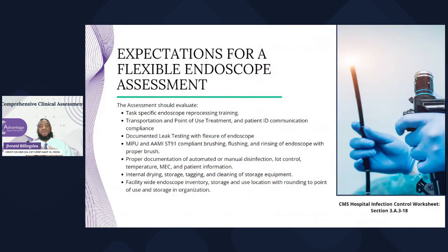And then we have good old flexible endoscope, one of my favorite areas. Again, do we have task-specific endoscopic reprocessing training? It's okay for people from SPD to do endoscopes, but they should have not just IFU access, but they should have training on each scope by the vendor, on all the equipment by the vendor, and document that training, right?